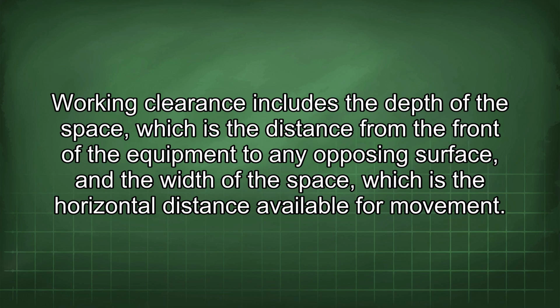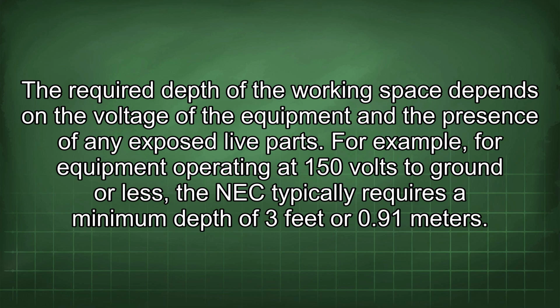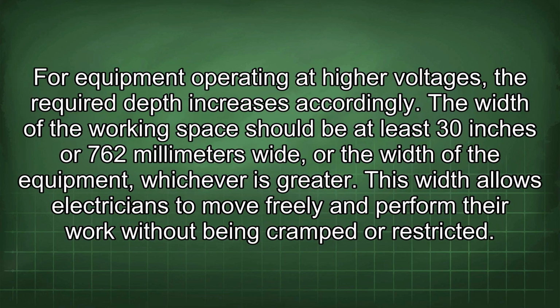Working clearance includes the depth of the space, which is the distance from the front of the equipment to any opposing surface, and the width of the space, which is the horizontal distance available for movement. The required depth of the working space depends on the voltage of the equipment and the presence of any exposed live parts. For example, for equipment operating at 150 volts to ground or less, the NEC typically requires a minimum depth of 3 feet or 0.91 meters. For equipment operating at higher voltages, the required depth increases accordingly.